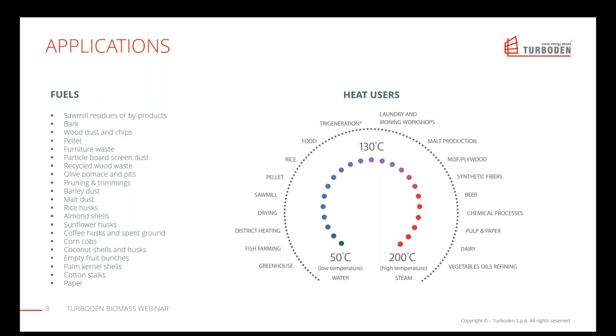or a combined cooling and power. So the heat out from the ORC condenser would be used to feed an absorption chiller. That could require 110 Celsius, 120 Celsius, so around 250 Fahrenheit, and even higher temperatures could be used. That may be what the MDF panel board requires, and the pulp and paper would require around 200 Celsius. The same temperature would be required in a dairy and vegetable oil refining. So 200 Celsius, we are around 420 Fahrenheit. That is steam, in the form of steam. Next, please.